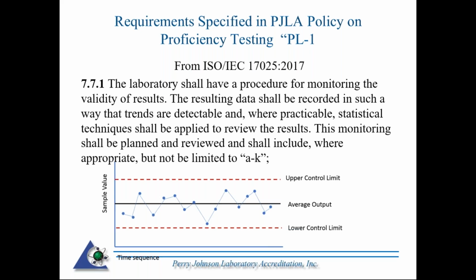You're required to have a procedure in place for monitoring the validity of results. So it's not just something you skip because you haven't covered it, perhaps it's a test or calibration that you rarely have, maybe a single customer prompts you to keep it on your scope of accreditation. You still have to assure that they are under control, and the validity of those results is also being monitored as per what can ever come under 7.7.1.